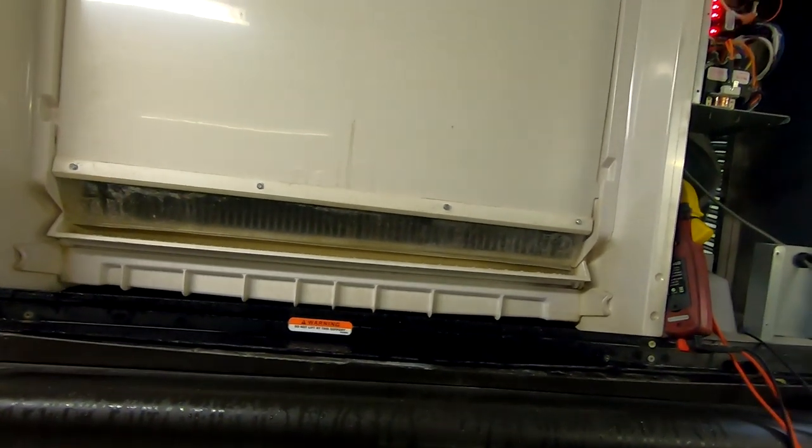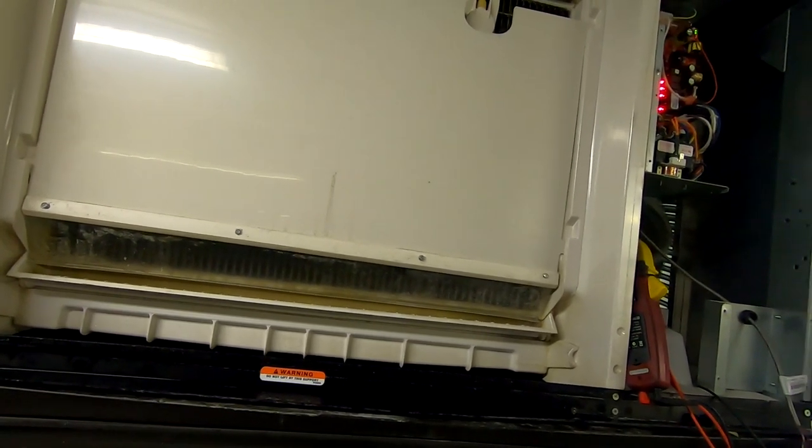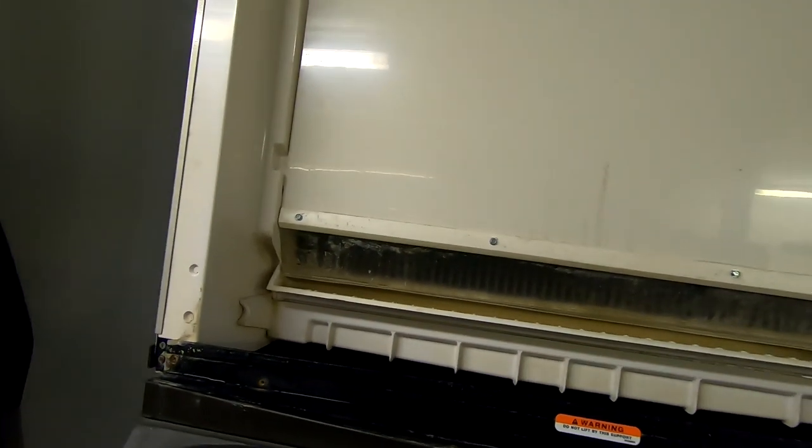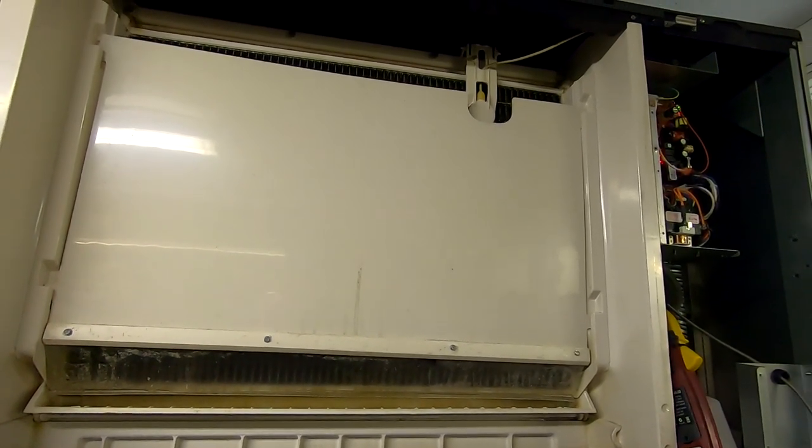I knew we wouldn't get that off. What I wanted to look at was to see if my evaporator plate was freezing uniformly all the way down to the bottom. And here's where I usually start my stopwatch. I want to see this thing drop generally in less than a minute and a half, two minutes max usually.